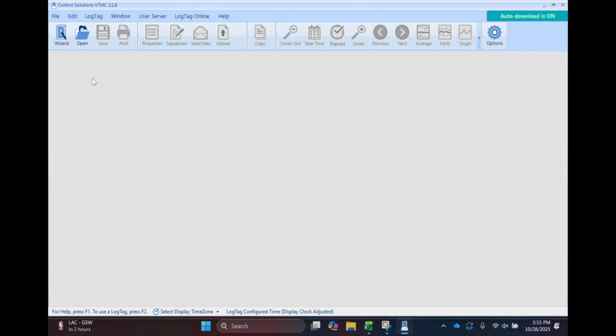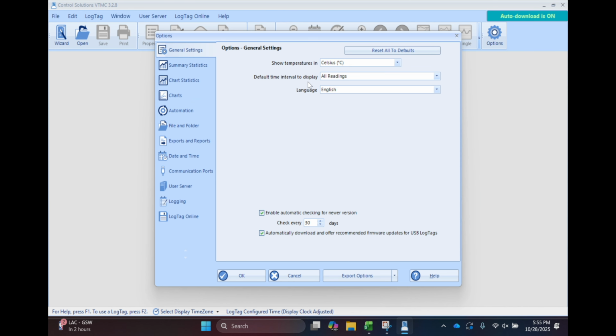So before you start your logger configuration, you're going to want to plan out whether you want to use Fahrenheit or Celsius for your temperature logging. If you want to use Fahrenheit, since all of our equipment is pre-configured in Celsius, open your software, click on Edit, select Options. At the very top it'll say Show Temperatures in Celsius - this allows us to change our software over to Fahrenheit if we wish. For today's demonstration, we're going to be staying in Celsius.